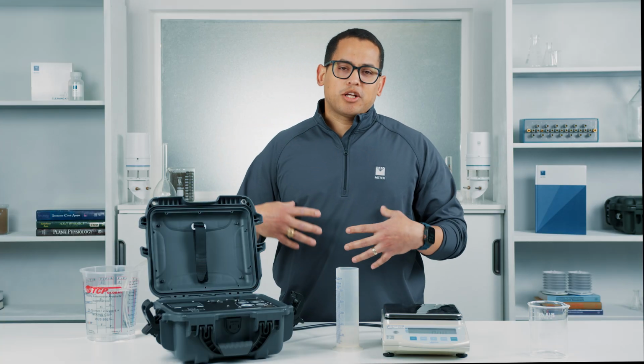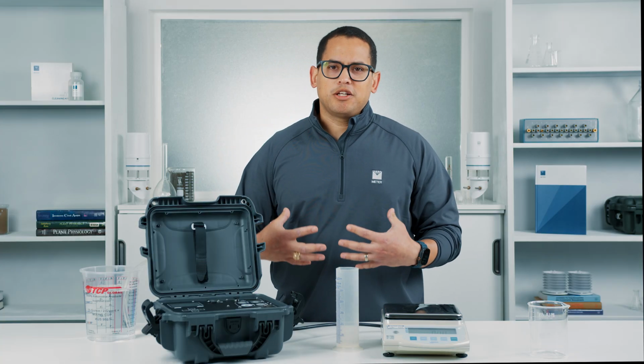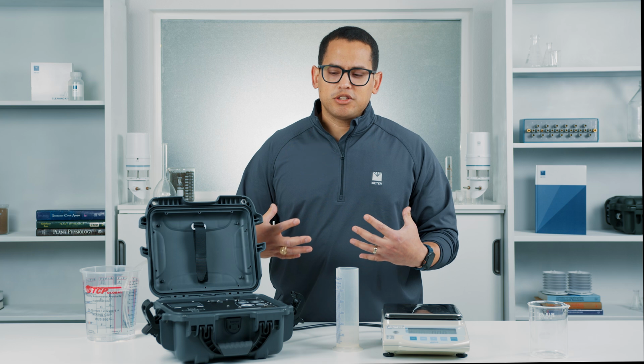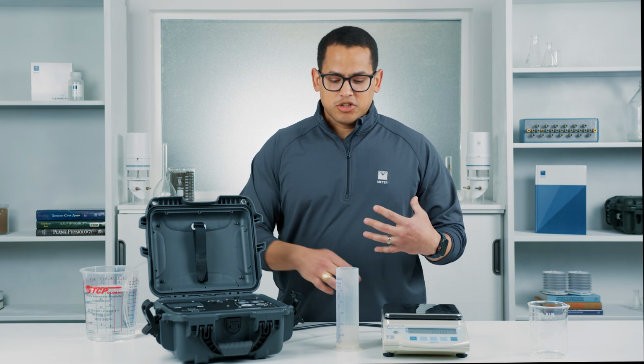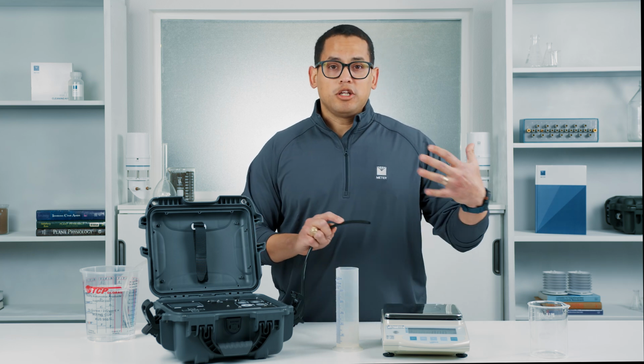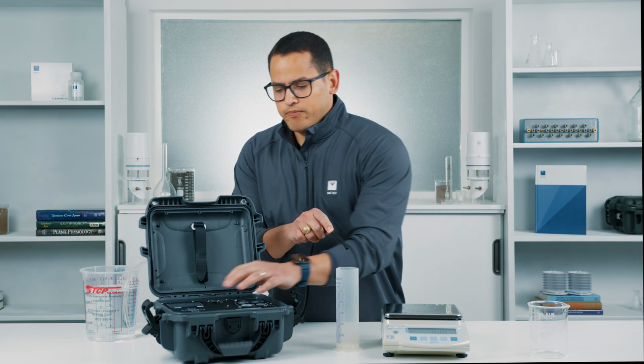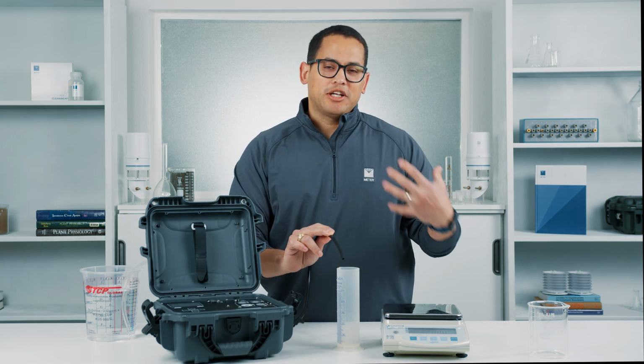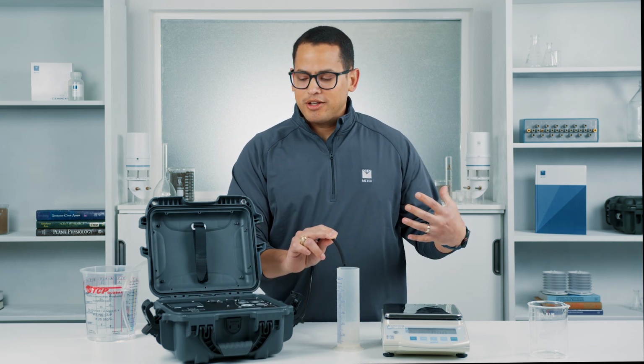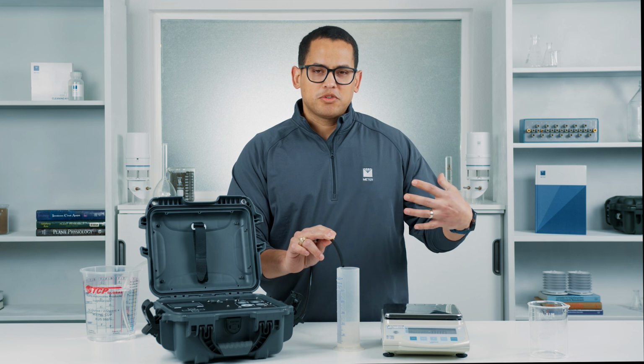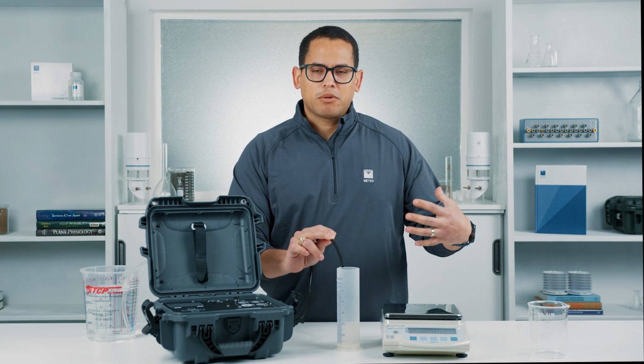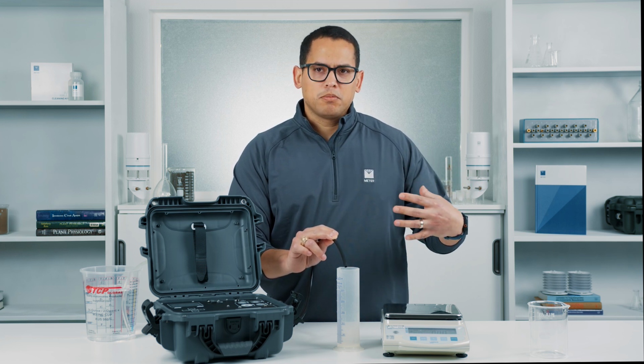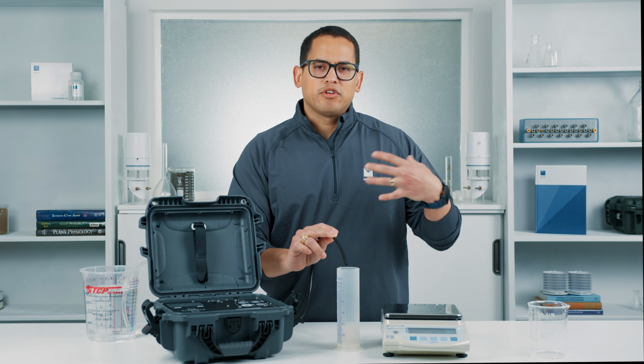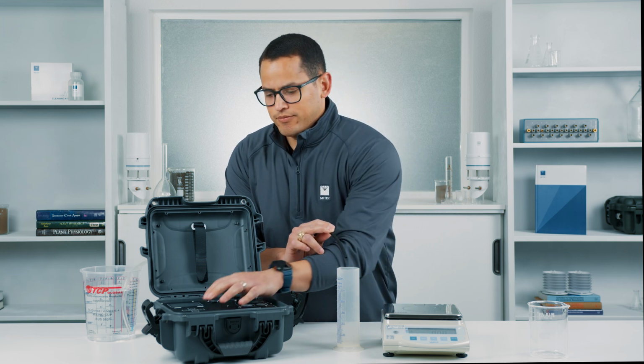It's going to ask you to check to make sure that you have the water supply line connected and that you have your reservoir ready to feed water into. We can go ahead and hit OK, and that's going to get us started on the purging of the line. So during the calibration, again, it's going to take multiple steps to purge the line. If you don't see that there's clean water with no air bubbles coming through the line, you'll just hit no multiple times until you have a cleanly purged line.